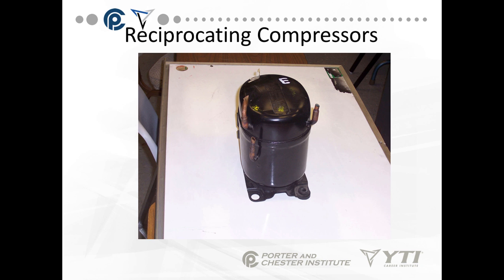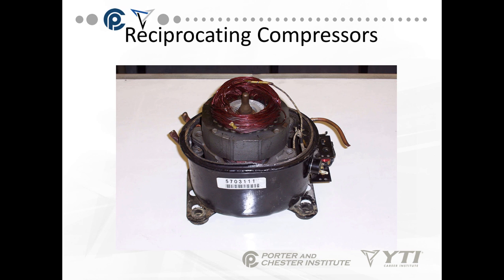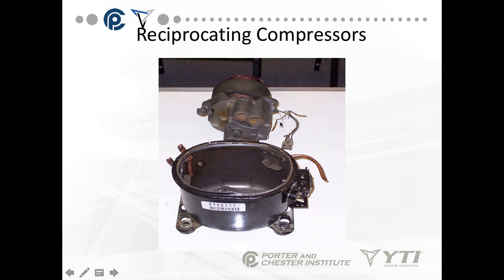You cannot service a hermetic compressor without cutting the shell open — the compressors are disposable. They're cooled with suction vapor. This is an example of a reciprocating compressor opened at the weld joint. You can see the motor, the windings, and everything inside. The start components go out here, and you have lines directly welded into the system. Down here, surrounding the motor, is where your valves are.